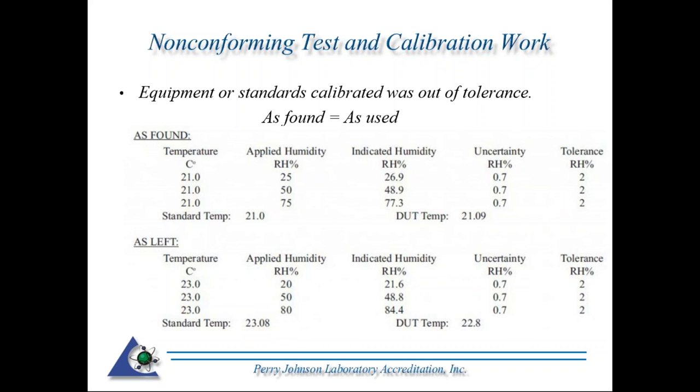And if you recall in section 4.6 in purchasing, there are requirements when you purchase supplies, you have approved vendors and suppliers, and when you receive them, they have to be inspected. Could be for specific properties, for reagents, could be specific grades or whatever. When those products or services are completed, you need to inspect them and be assured you got what you in fact ordered. So for calibration, typically what that's going to be is a calibration report.